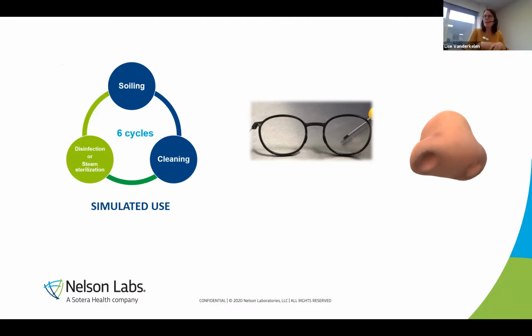Sometimes I put a nose on the slide. We have seen cleaning validation where we put the device in simulated use and everything looks clean. But the technician came to me and said, but it smells strange. It doesn't smell good anymore. That also shows you that something is wrong. So please broaden your mind there. If it looks clean, but it smells strange or it feels different, I would already say stop there and see what is happening before you continue, because these things will happen in the healthcare facility for sure, perhaps after 12 cycles, because it's not so worst case, but still it will happen.